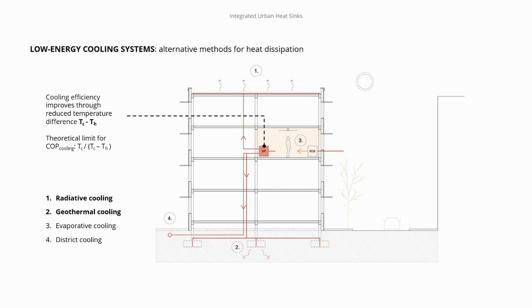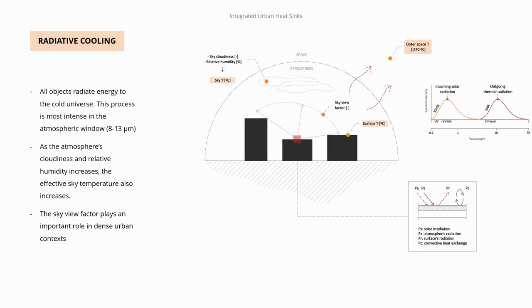Both systems assume you have a cooled slab with water pipes in it. Where does that water go to reject the heat removed from the building air? For the radiator system, it goes to the roof, with the radiator rejecting heat to the night sky. For the geothermal system, it goes to the ground to a heat exchanger associated with the structural footings of the building. We do not consider evaporative cooling and district cooling.